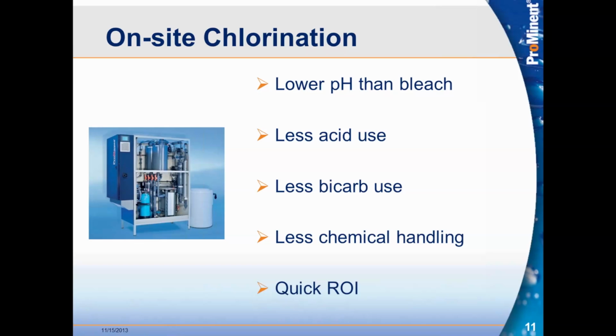It takes that high concentration brine and transforms it into a batch of sodium hypochlorite, bleach. So as the system makes the bleach, or as your pumping system utilizes the bleach, this system will make up the bleach that's being pumped into the pool for disinfection and oxidation purposes. The benefits of an on-site system are multifold in that the solution of bleach manufactured by this system is lower pH than delivered bleach. It's about 10.5 as opposed to 13 for delivered bleach. And again, going back to the smart disinfection, this results in less acid use, which translates into less bicarb use, and also obviously translates to less chemical handling.